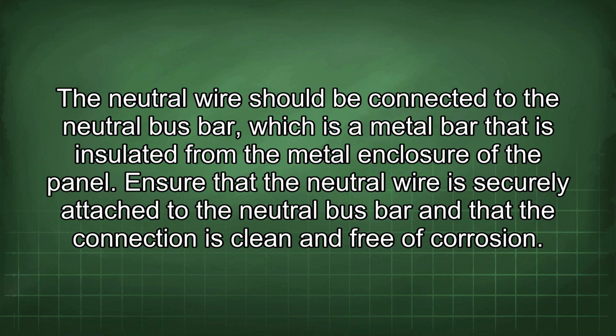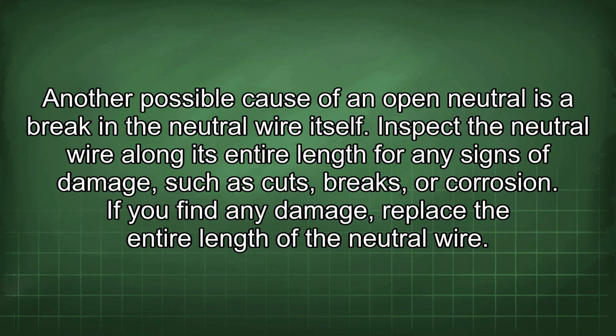Another possible cause of an open neutral is a break in the neutral wire itself. Inspect the neutral wire along its entire length for any signs of damage such as cuts, breaks, or corrosion. If you find any damage, replace the entire length of the neutral wire.